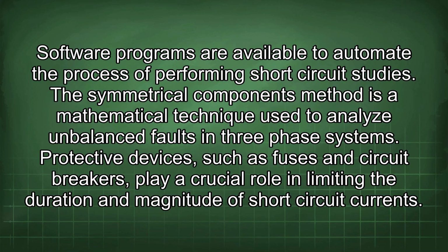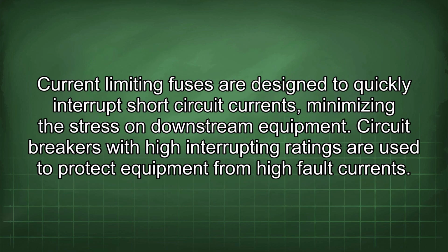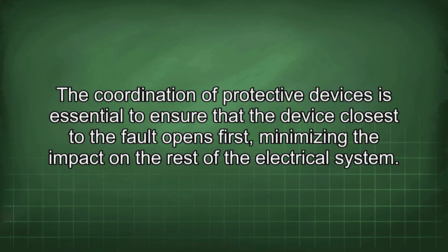Protective devices, such as fuses and circuit breakers, play a crucial role in limiting the duration and magnitude of short-circuit currents. Current-limiting fuses are designed to quickly interrupt short-circuit currents, minimizing the stress on downstream equipment. Circuit breakers with high interrupting ratings are used to protect equipment from high fault currents. The coordination of protective devices is essential to ensure that the device closest to the fault opens first, minimizing the impact on the rest of the electrical system.